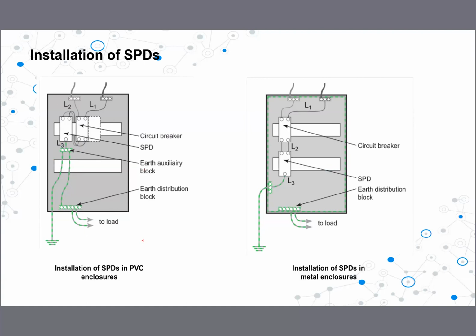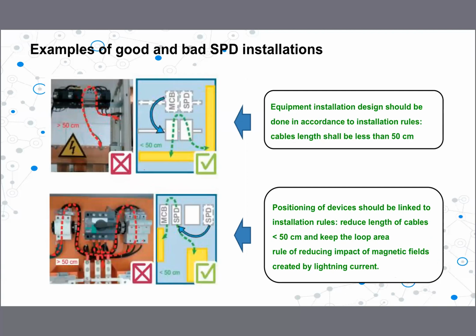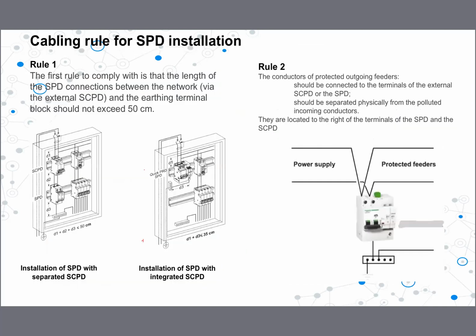Then these are also correct installation practices. Somehow what we need to achieve is to reduce the length of the cable from the live terminal to the earth terminal, right? Then there are 2 rules when you do a proper SPD installation, right? First one is to comply with the length of the connection between the network via the SPD and the terminal block, which should not exceed 50. We discussed this already, right?